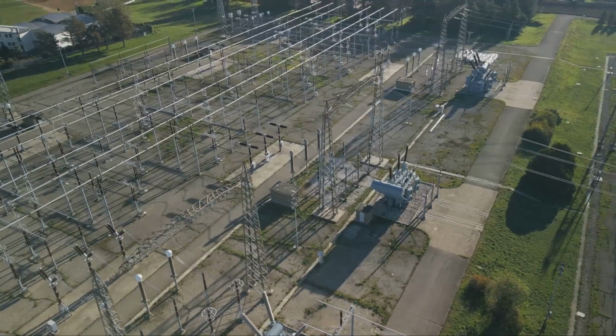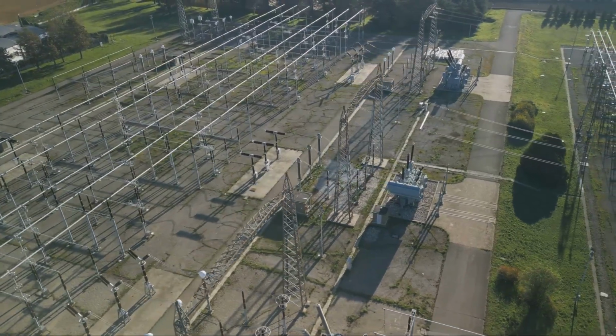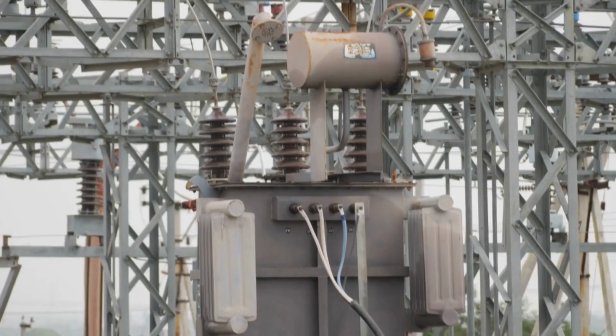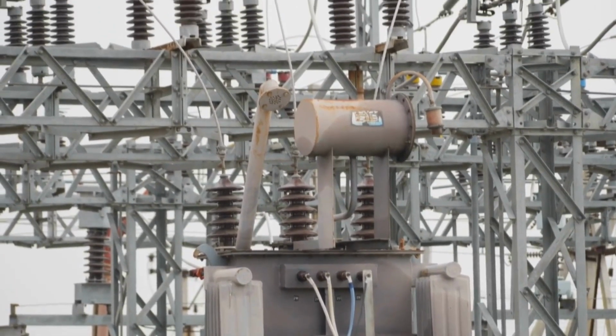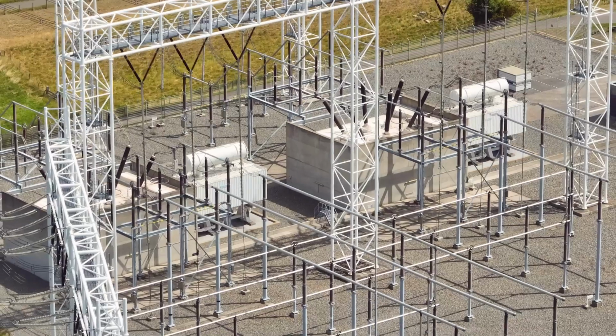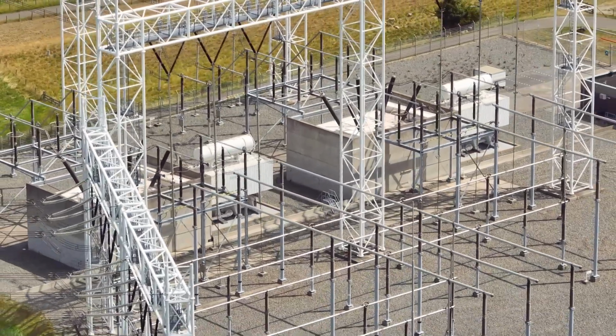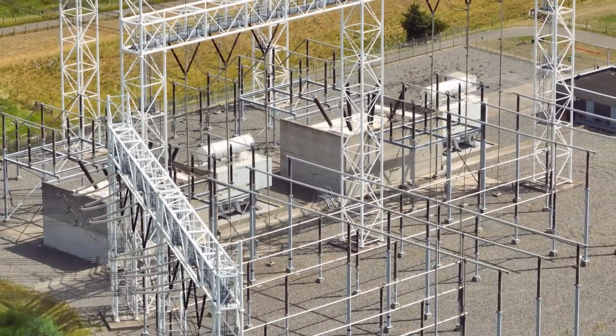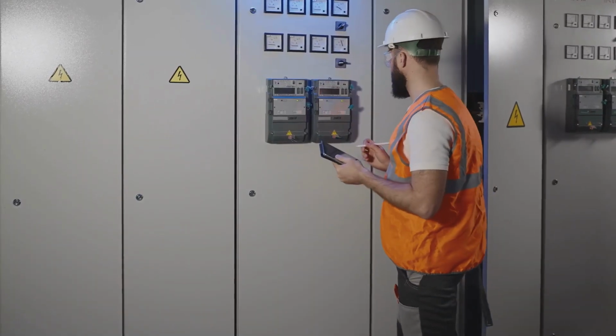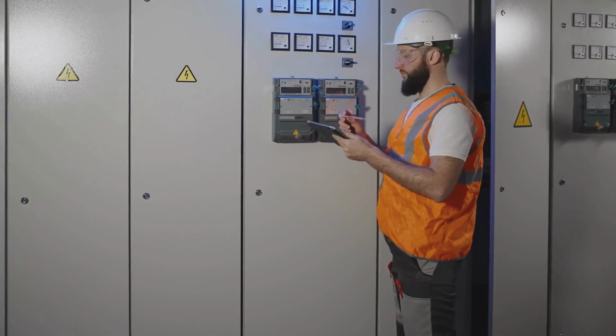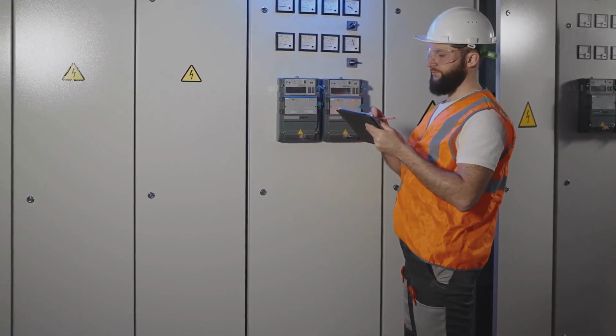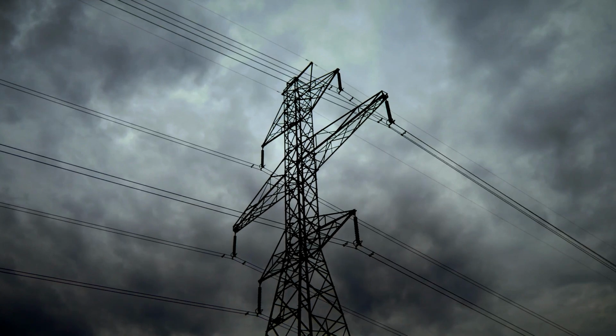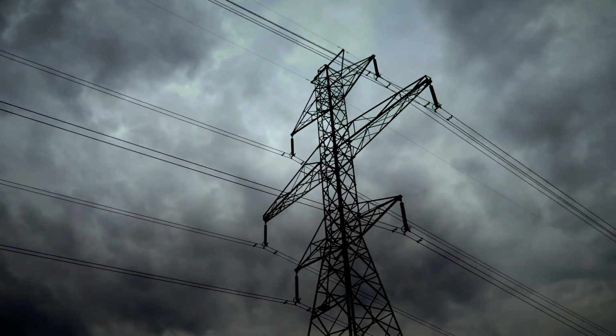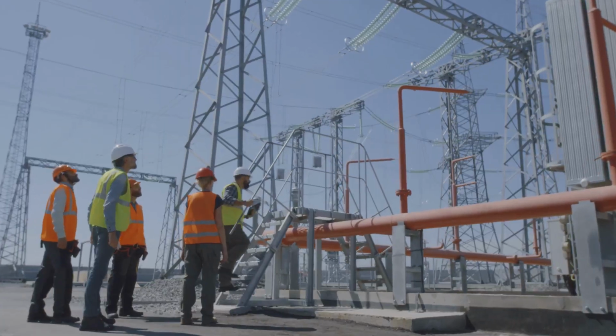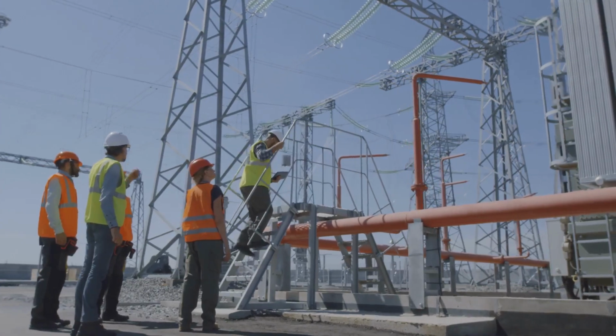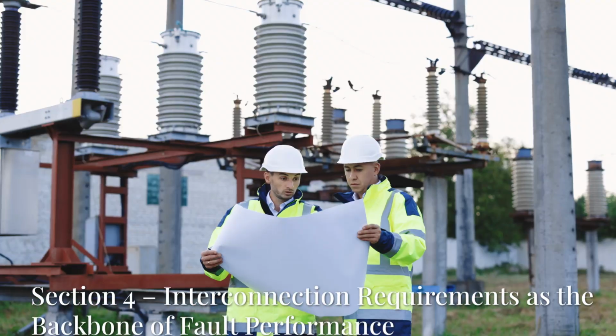This section also introduces the reference point of applicability, or RPA. This is usually the point of common coupling, the point where a customer system meets the utility's grid. All requirements for voltage, frequency, power quality, and protection apply at this interface. That's a critical distinction. A DER might internally manage its behavior, but only its external performance at the PCC matters for compliance. So when we think of FRT, it's the DER's ability to maintain grid-compliant output at the PCC during abnormal system events that determines its contribution to reliability.